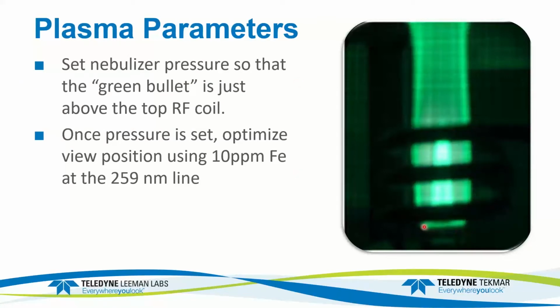So the green bullet, which is this little finger that's coming up, is just slightly above that coil, and it doesn't show up all that well. And then once we have the pressure set, we optimize the view position by running a 10 ppm iron solution, or one of the standards, at the 259 nanometer wavelength line, and that sets the observation height for the analysis.